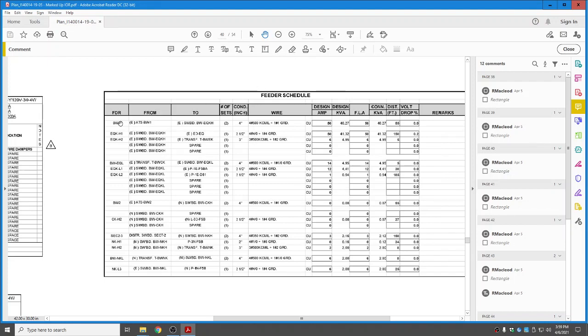So remember we were talking earlier, we showed that symbol in the hexagon. Let's take a look here. Let's jump down to BWEQL, transformer, number of sets 2, conduits 4 inch, 2 4-inch. The wire's going to be 4 number 600 kcmil and a 1 number 1-aught ground in each of those 2 conduits. It's a copper wiring. It's going to give us the amperage and some additional information. What's most important on the feeder schedule to us is it shows the conduit size and the wire size between different pieces of larger equipment.